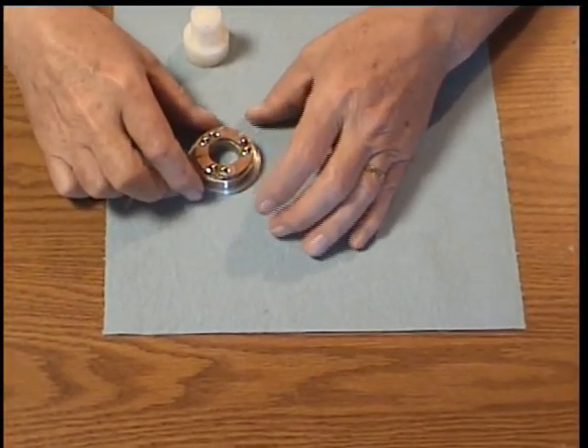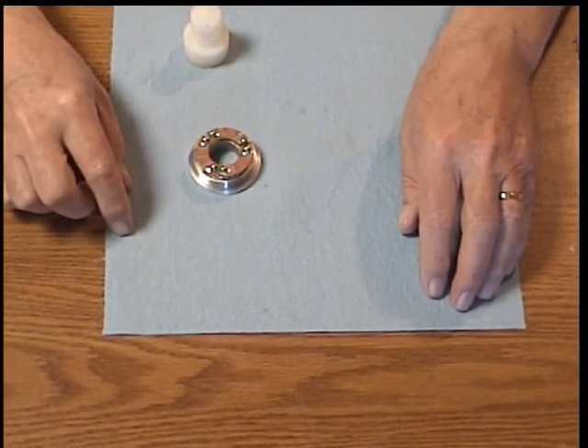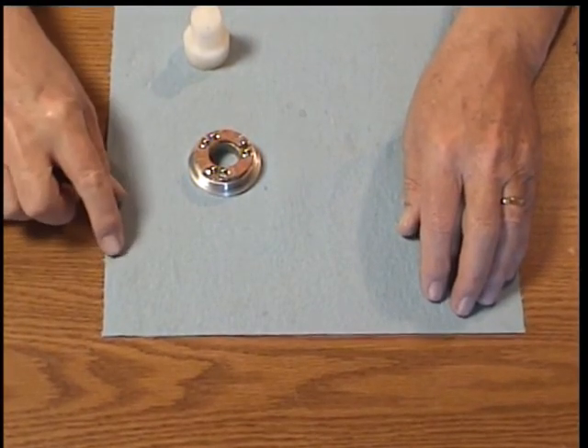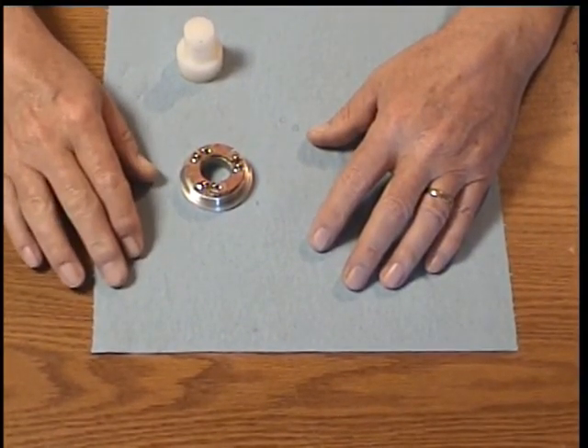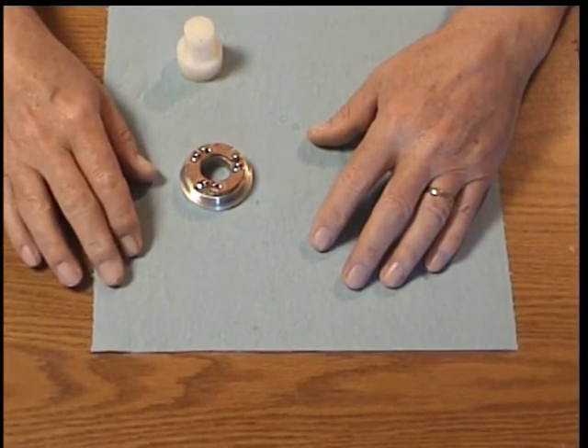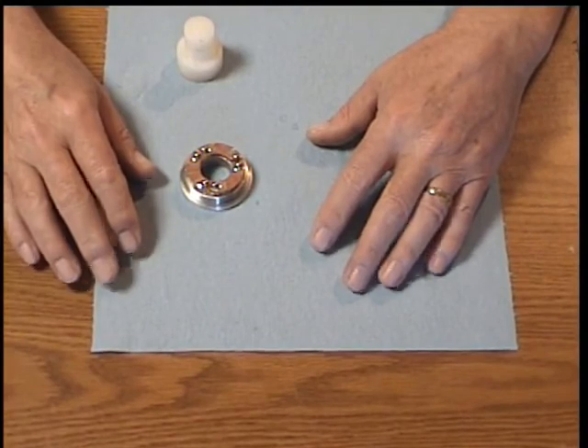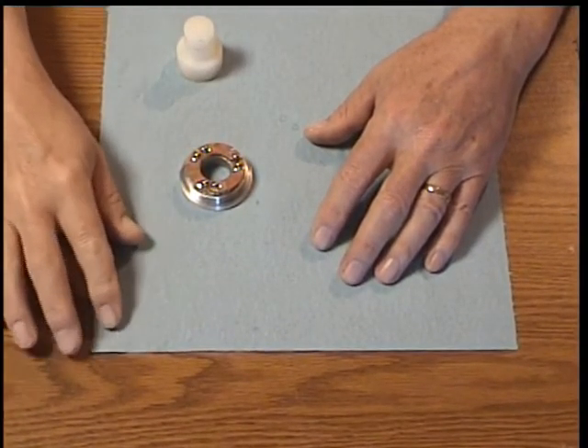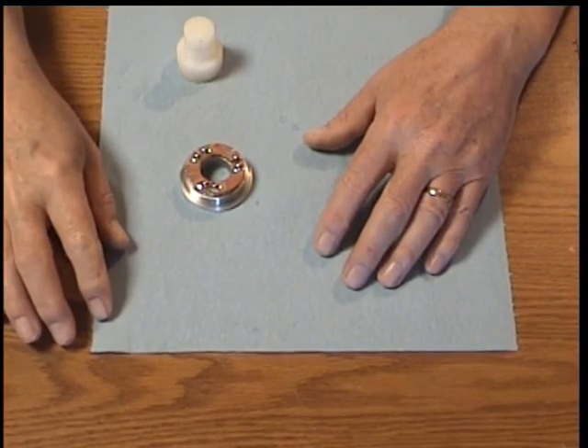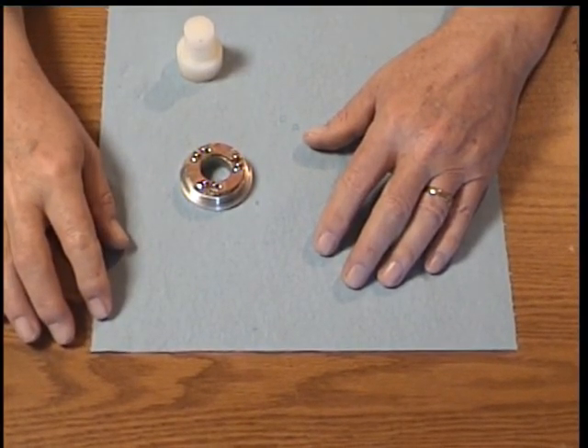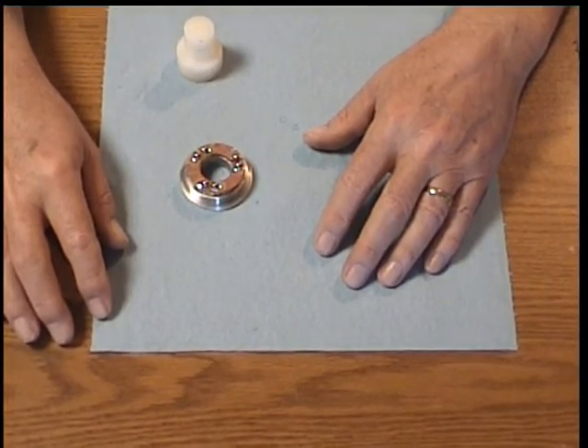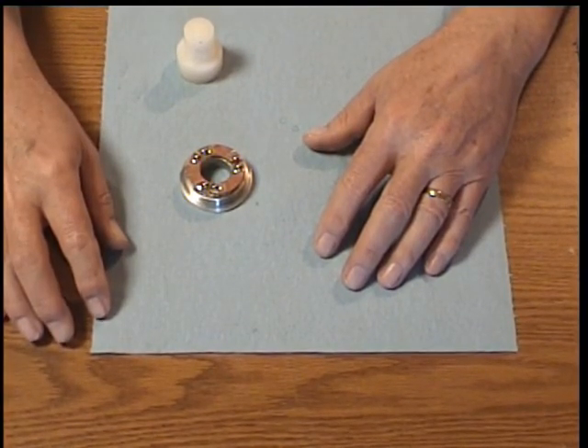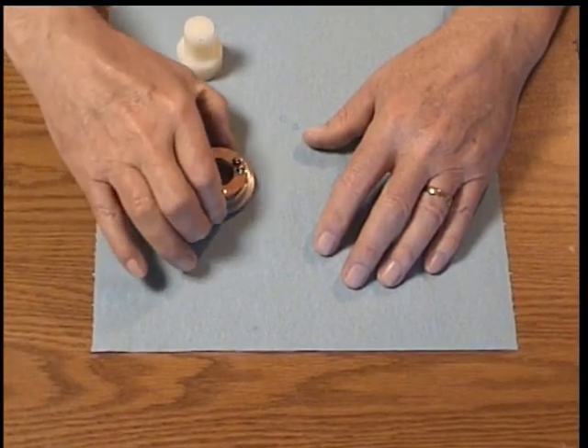This needs to be set aside and allowed to dry. 24 hours is the best situation. You can push it at about 8 hours. But if you continue the work after 8 hours and you actually complete the job before 24 hours has elapsed, you increase the chance that the silicone adhesive will not have cured fully and may break loose in the process of adjusting the probe as we go down further in the assembly process. So, as I said, the best situation is to let this set for 24 hours.